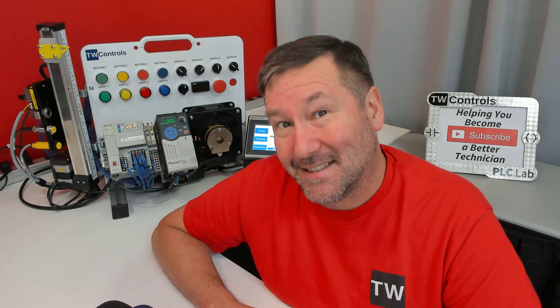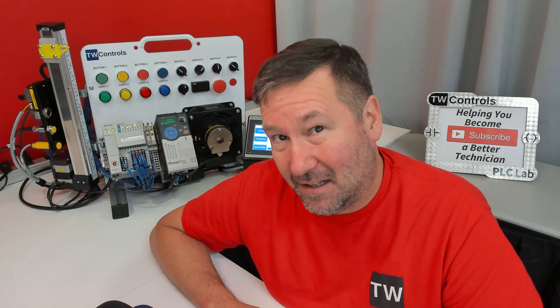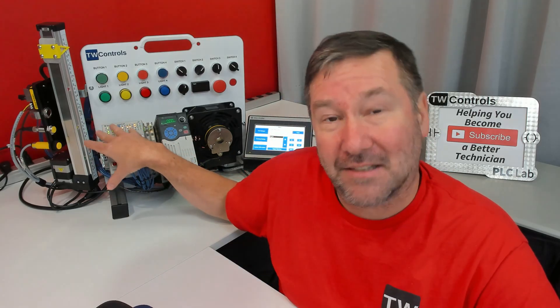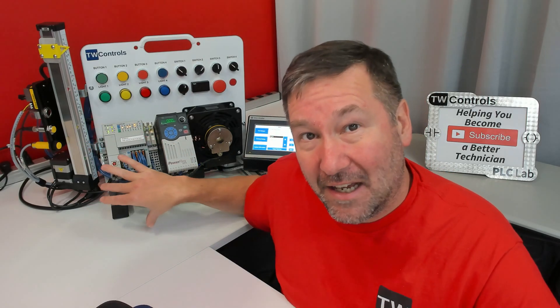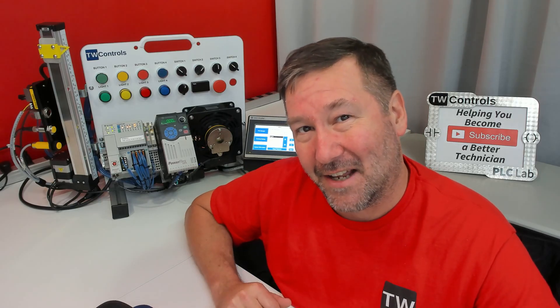Today we're going to talk about what happens when you accidentally enable DLR on a Compact Logix PLC or any DLR capable PLC and you're not actually on a DLR network.